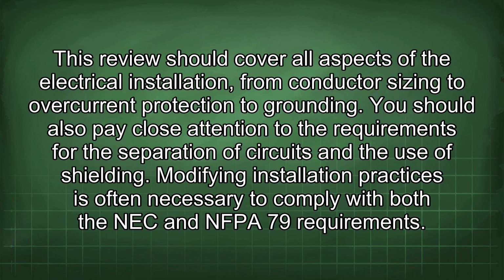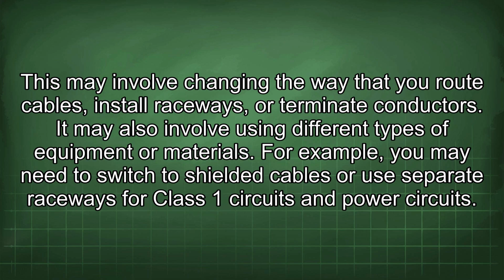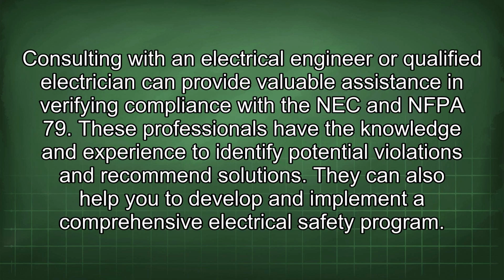Modifying installation practices is often necessary to comply with both the NEC and NFPA 79 requirements. This may involve changing the way that you route cables, install raceways, or terminate conductors. It may also involve using different types of equipment or materials. For example, you may need to switch to shielded cables or use separate raceways for Class 1 circuits and power circuits.